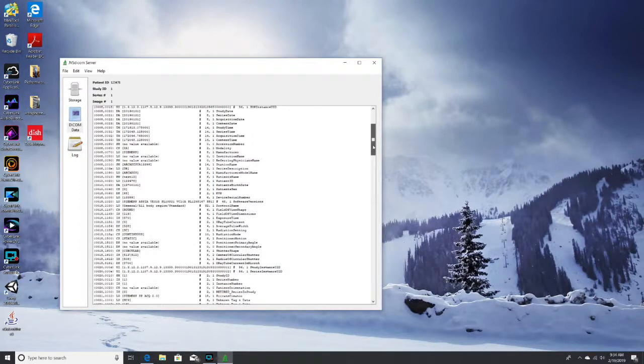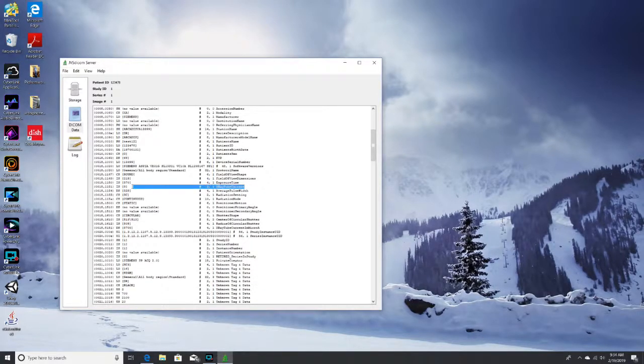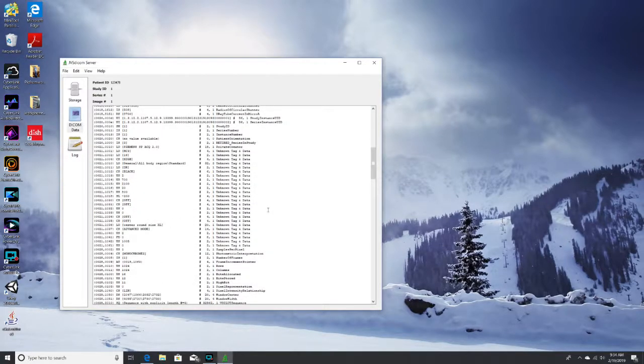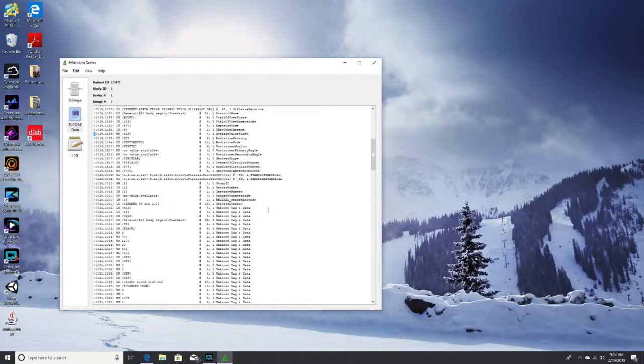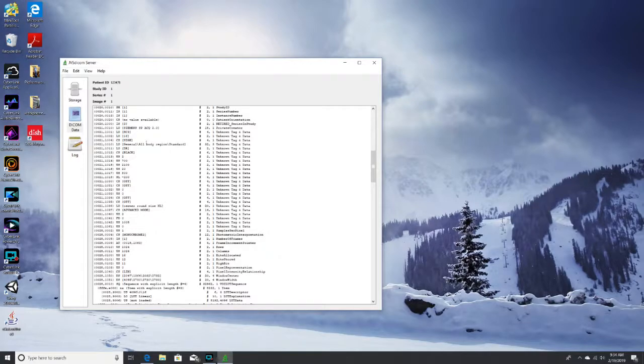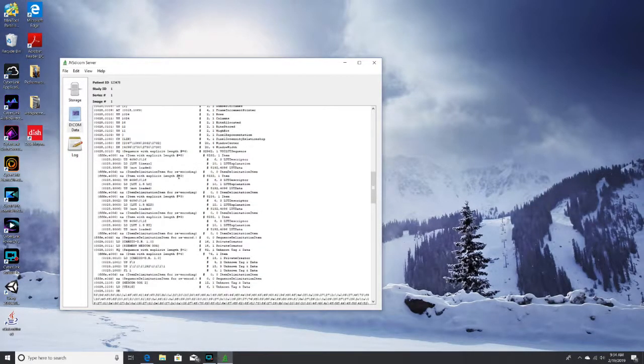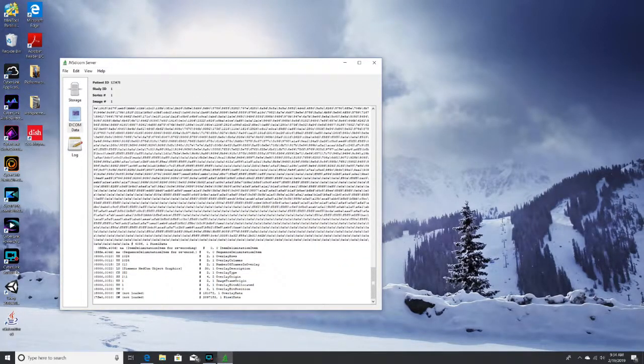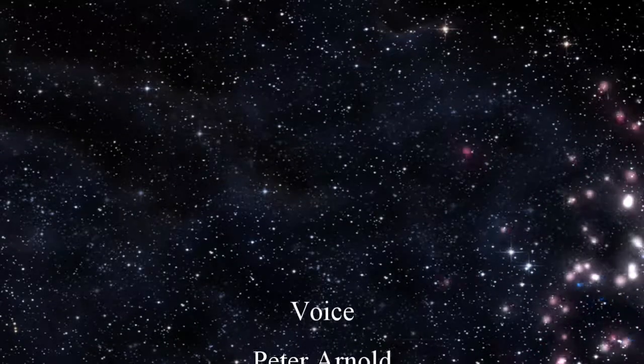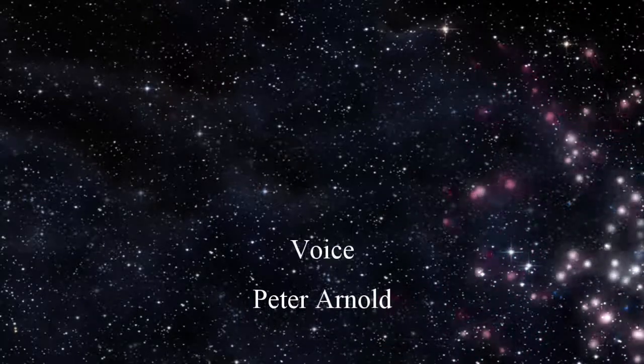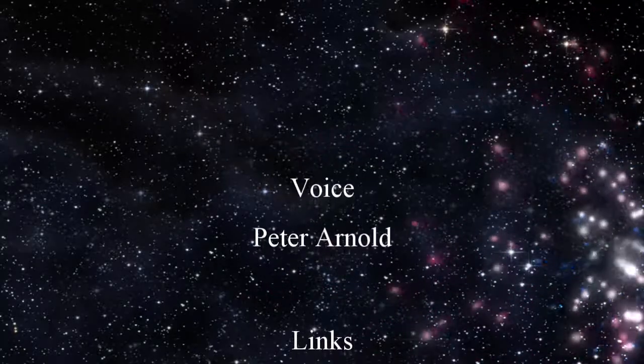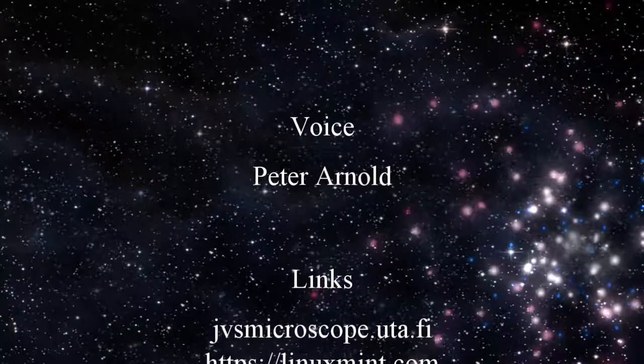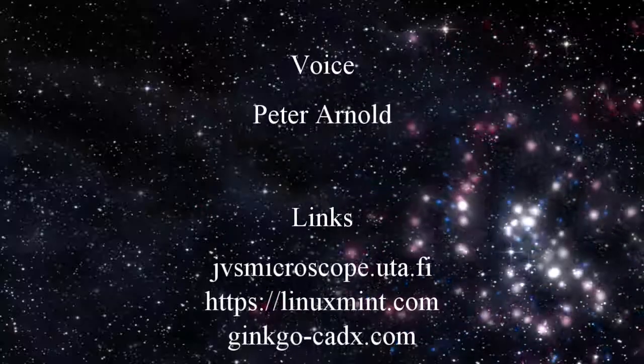I hope this video helps with any Dicom issues that you might have. This emulator will help you to eliminate a machine issue, C-arm, X-ray machine, or workstation issue. Basically, if you can send your Dicom image through a Cat5 crossover cable or through a hub directly to your emulator, you should be able to send to PACS. Issues could be wrong information inputted in the unit, such as an AE title or IP address. Issues could be something in between with IT, a switch possibly, but most likely it will not be the machine. If you can send to this through a switch or through a crossover cable, you should be good to go.